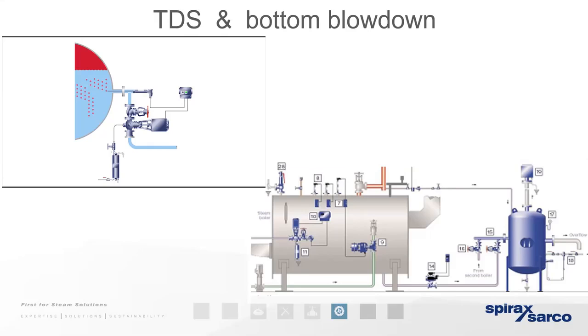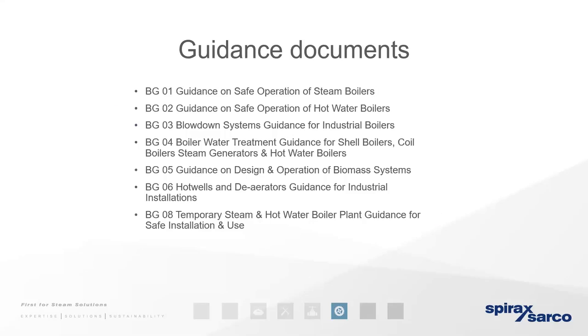TDS blowdown is performed similarly to bottom blowdown but taken from the side of the boiler. We can automate it to ensure the best possible steam condition and avoid blowing down more than the prescribed amount. Steam operators have health and safety guidance documents — the key word being 'guidance.' There's no obligation to observe them, but if a severe failure or health and safety incident occurred, questions would be asked if guidance had not been followed.